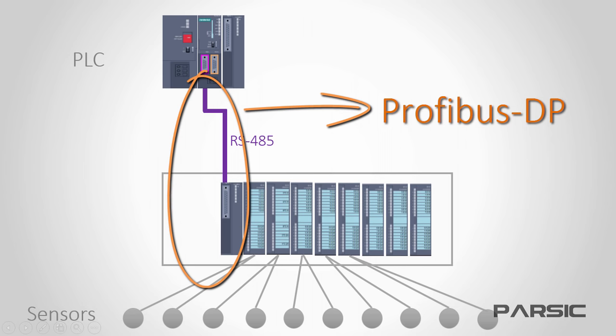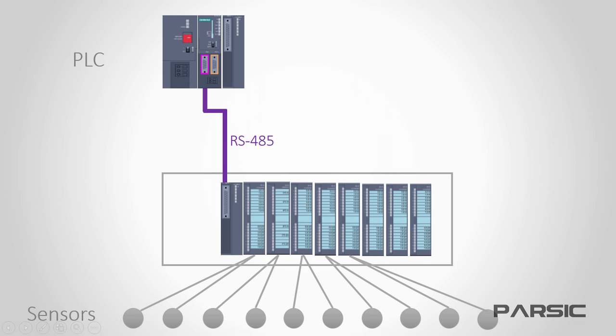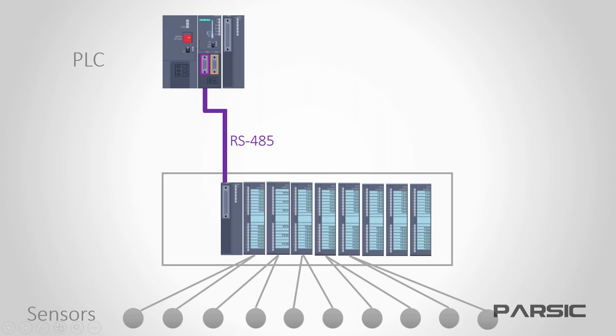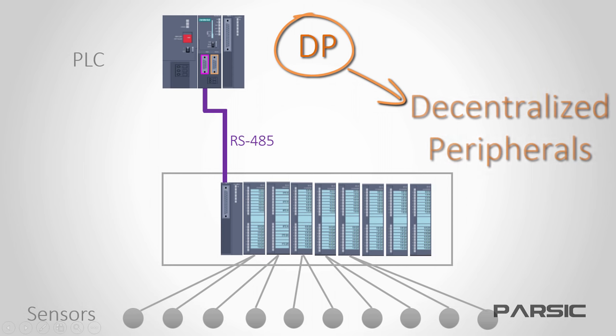Previously, the PLC's I.O. modules were arranged centrally, but by introducing a network bus between the main controller and its I.O. modules, we decentralized the I.O.s, moving them to this enclosure in the field area. That's why this type of Profibus has the added suffix of DP, or decentralized peripherals. We usually call these decentralized peripherals remote I.O.